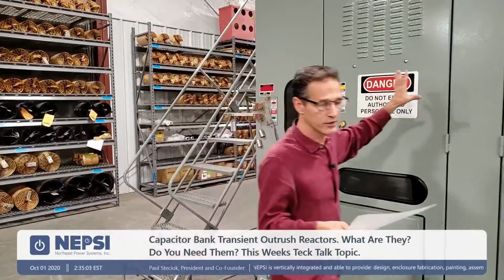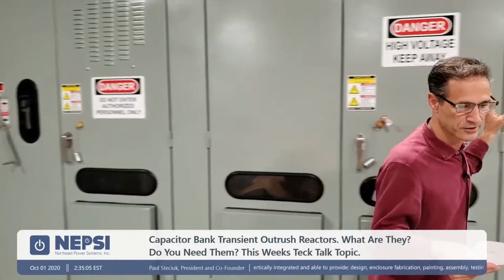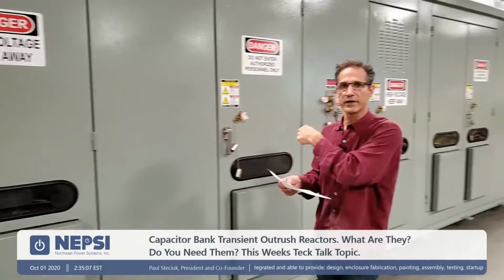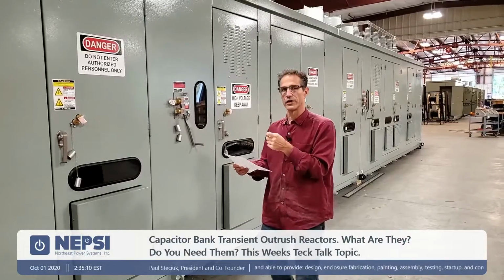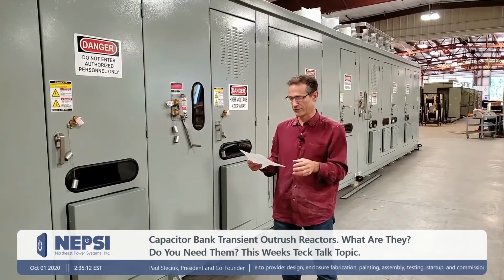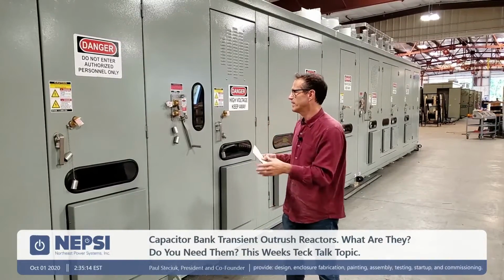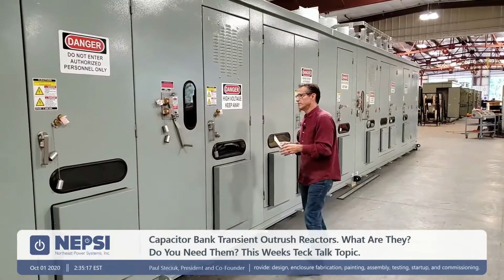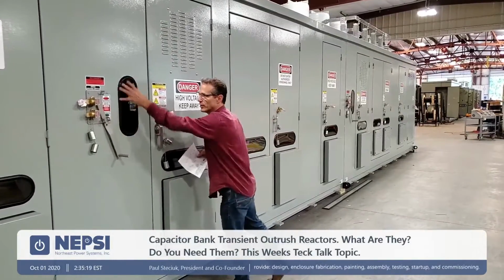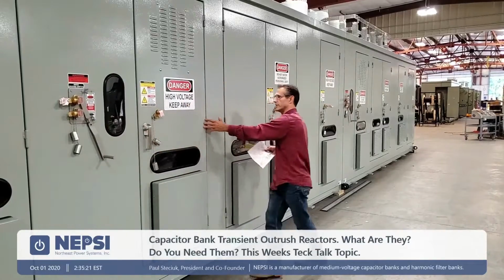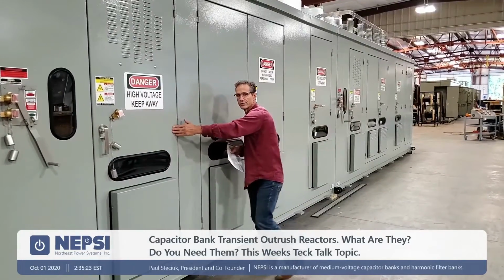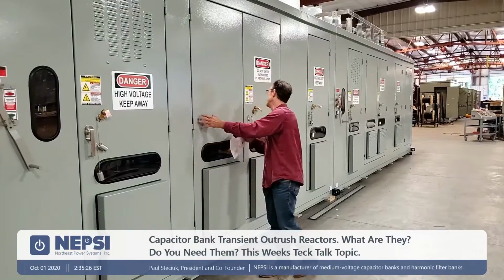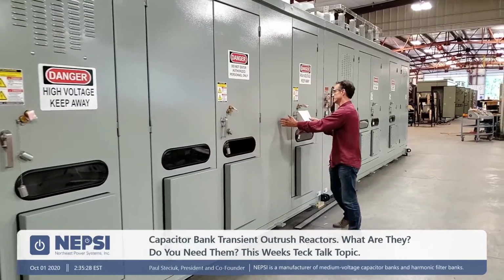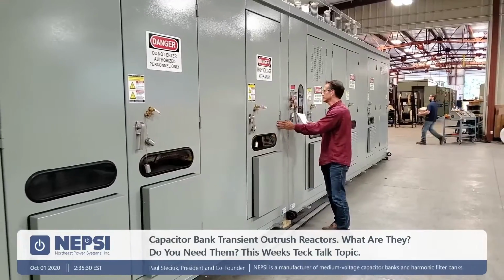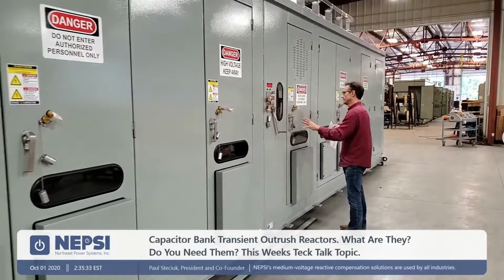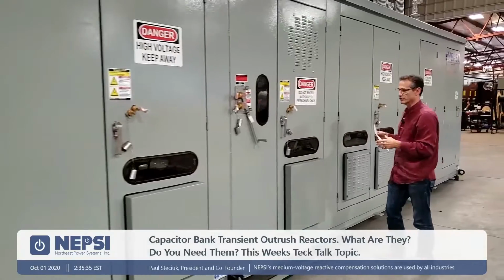This is a 40.5 MVAR capacitor bank, 34.5 kV rated, and it's got a BIL rating of 185 kV BIL. So it's a three-stage bank, and we're going to walk along here. You can see this is stage 2. We got a window and a ground switch, and then we got a switching device. We're going to talk about this switching device today. It's a VD4CS, and then we have another, in this case, 13.5 megavars, another ground switch, and then a switching device.